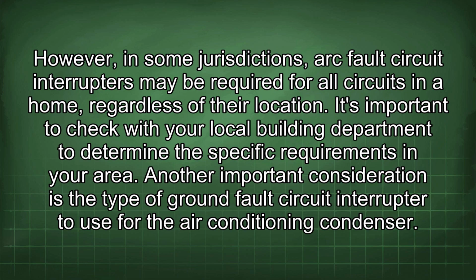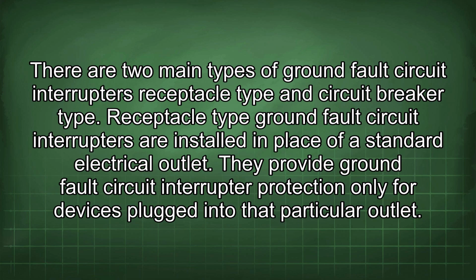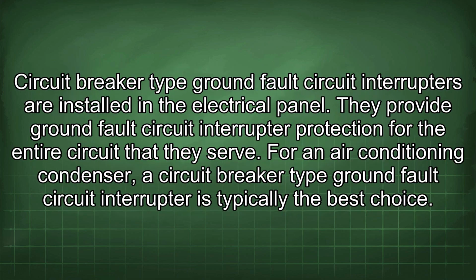Another important consideration is the type of ground fault circuit interrupter to use for the air conditioning condenser. There are two main types of ground fault circuit interrupters: receptacle type and circuit breaker type. Receptacle type ground fault circuit interrupters are installed in place of a standard electrical outlet. They provide ground fault circuit interrupter protection only for devices plugged into that particular outlet. Circuit breaker type ground fault circuit interrupters are installed in the electrical panel. They provide ground fault circuit interrupter protection for the entire circuit that they serve.